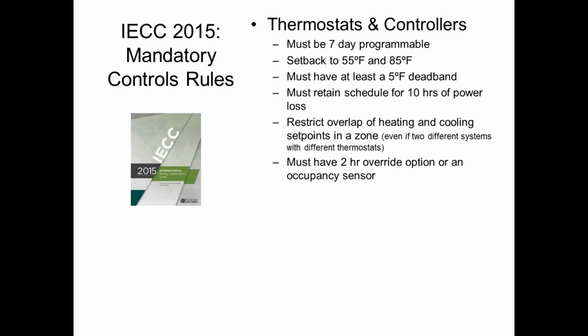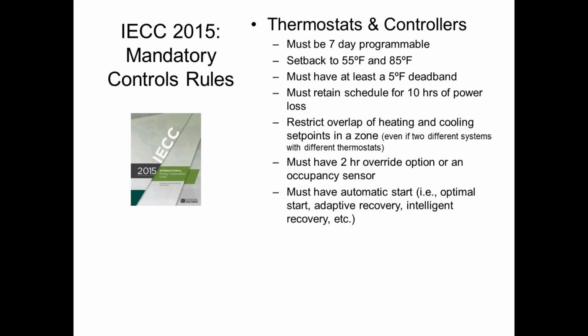You've got to prevent the heating and cooling set points from overlapping. There's got to be an override button, normal things. They've got to have automatic start control. Manufacturers call this different stuff: intelligent recovery, smart recovery, adaptive recovery, optimal start, things like that, which basically means you tell the system you want to go occupied at 8 a.m. It calculates, based on previous history and/or weather data, if it needs to start at 7:02 to get to set point at 8 o'clock, or if it needs to start at 7:30 or 6:51. So it starts each day at a different time to get you to set point exactly at the time you asked for. Your thermostat has to be able to do that for code.